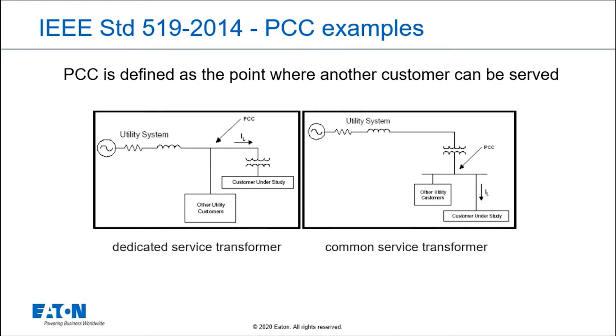The PCC, or point of common coupling, is really critical to understand — that's the point where another customer could be served. This standard makes the utility the mediator for when things go wrong. So if I, as one customer, create harmonics and you, as another customer, get the distortion I've created causing problems on your load, the utility has to be the mediator. The PCC is typically where the utility can serve another customer — usually the secondary if multiple customers are fed, or the primary if you're the only customer on that transformer.